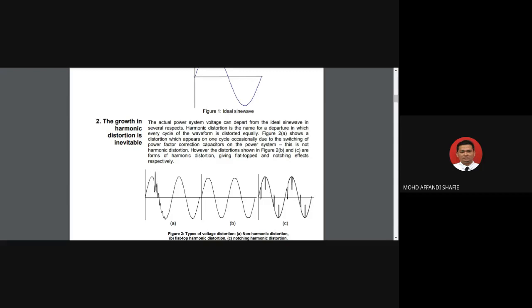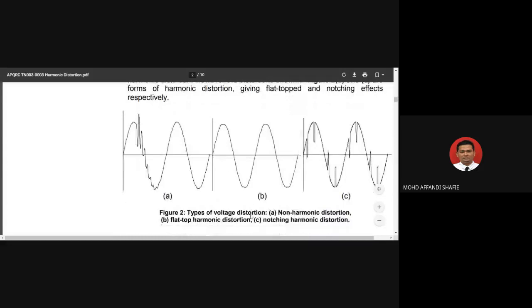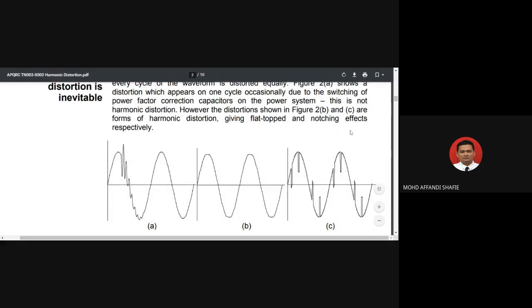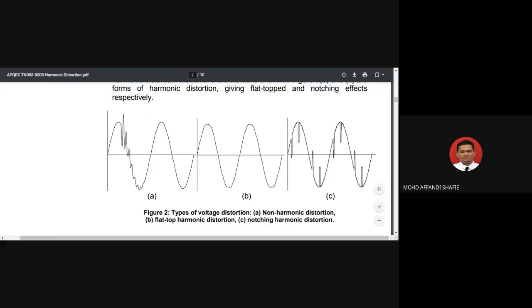However, the distortion shown in figure 2B and C is a form of harmonic distortion, giving flat top and notching effects respectively. So flat top here, you can see what the flat top is. You can see it at the highest value of this sine wave. Then the other one is from figure C, the notching effect. For each single cycle you can see the notching effect in the waveform. So B is the flat top harmonic distortion, and C is a notching harmonic distortion.